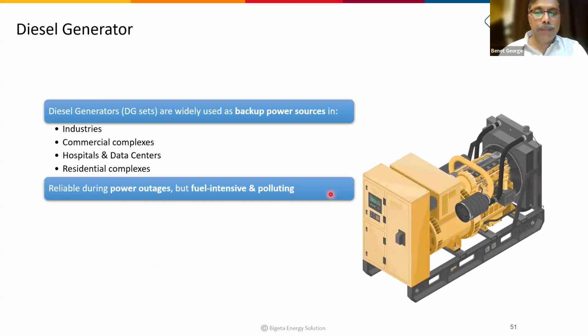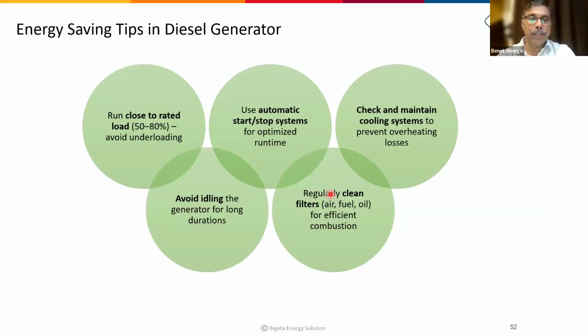Another equipment is the DG set, the diesel generator set. It is used as a backup power source in many organizations. So we have to remember that this may be one of your highest GHG emission sources. Then the same opportunities apply in diesel generators: see whether we can operate at 50 to 80% load, which may be the more efficient condition.